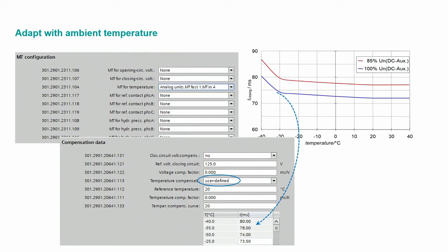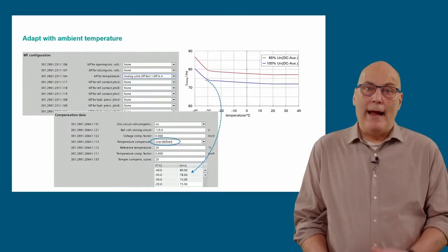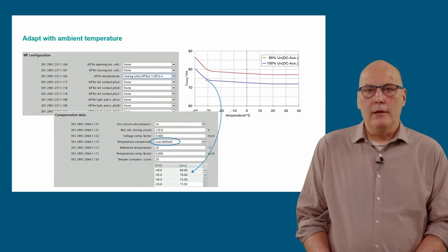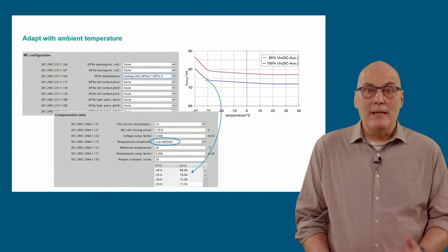If compensation of the closing time due to ambient temperature is required, this can be implemented with a temperature sensor connected to a transducer input. Configuration is done by selecting the corresponding transducer and choosing a linear or user-defined compensation. For user-defined compensation, setting points from the characteristic curve can be entered. The curve shows two influences on closing time — temperature and control voltage. Control voltage has a linear influence between 85 and 100% of nominal voltage, considered separately. Temperature compensation is assumed at nominal voltage over the horizontal temperature range from minus 40 degrees C to plus 40 degrees C.